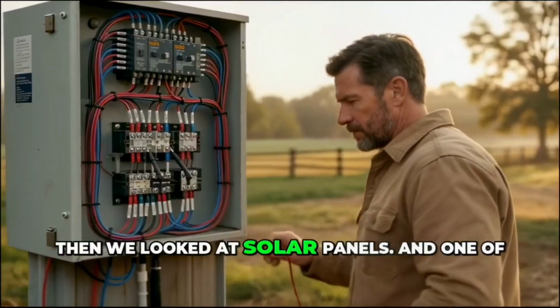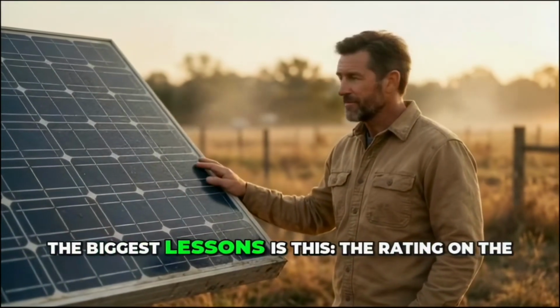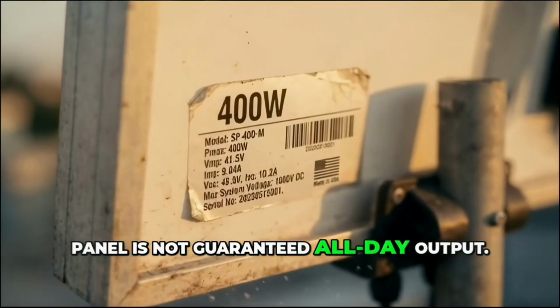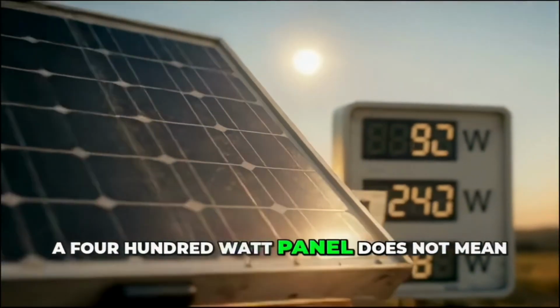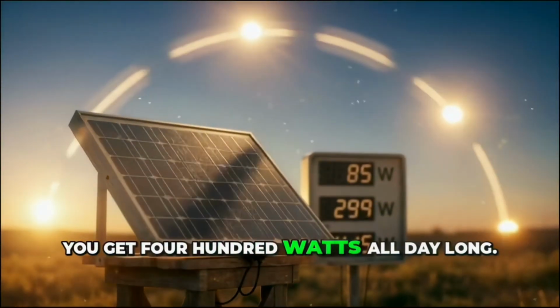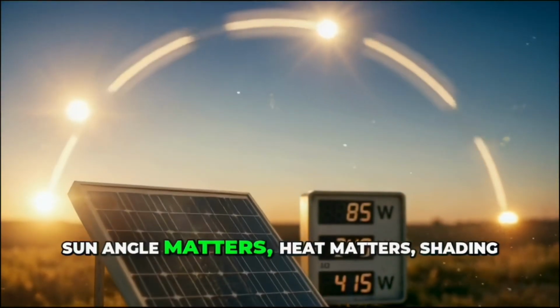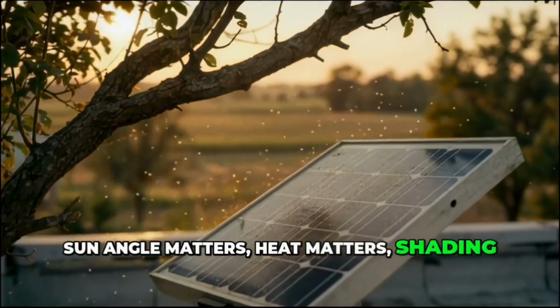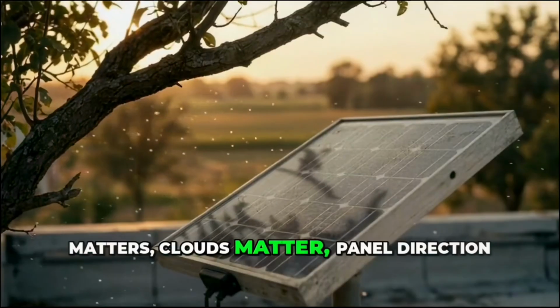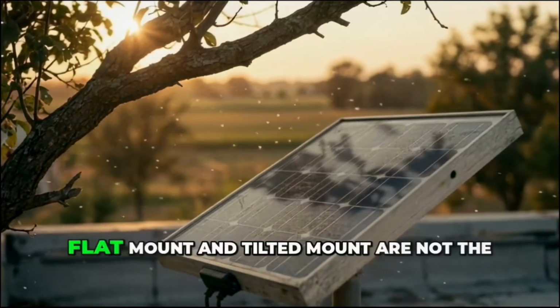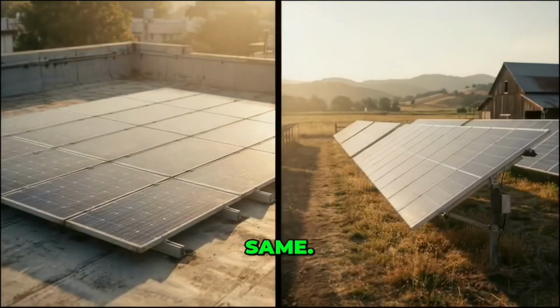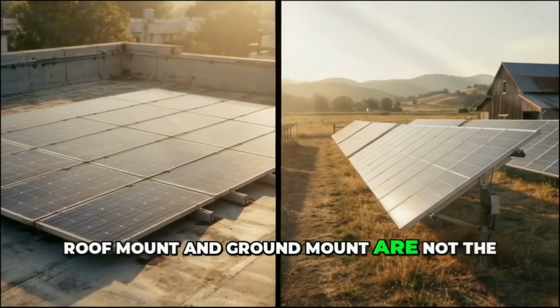Then we looked at solar panels. And one of the biggest lessons is this: the rating on the panel is not guaranteed all-day output. A 400-watt panel does not mean you get 400 watts all day long. Sun angle matters, heat matters, shading matters, clouds matter, panel direction matters, flat mount and tilted mount are not the same. Roof mount and ground mount are not the same.